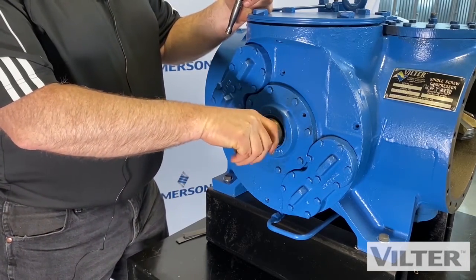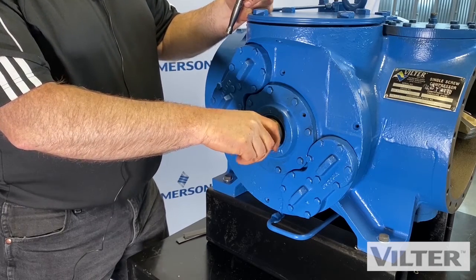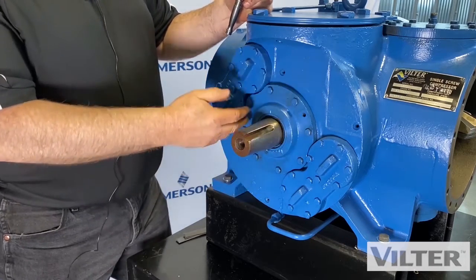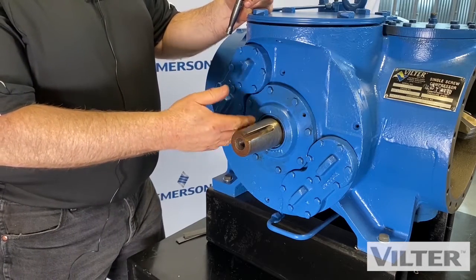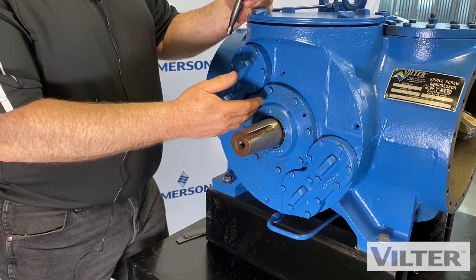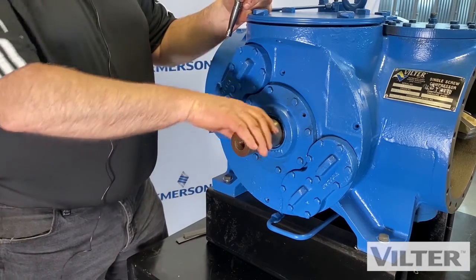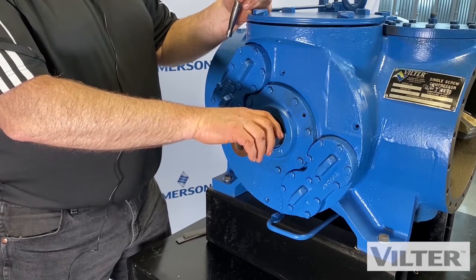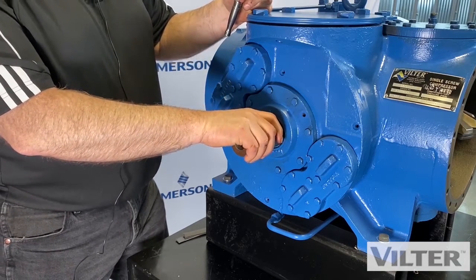Most of the time the leaking refrigerant would happen when the machine is shut off, because the seal area is always full of oil. The oil is used for cooling and lubrication, and it helps seal as well. To change the shaft seal, we're going to have to remove all the refrigerant, lock out, tag out, and follow all those procedures that we talked about earlier.